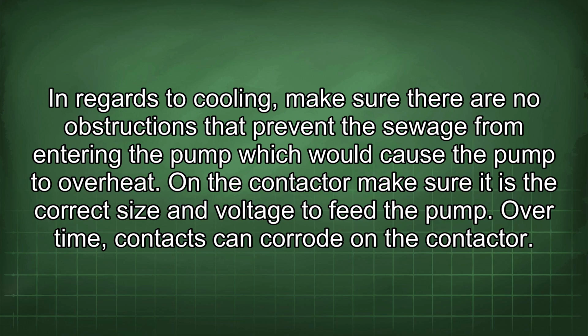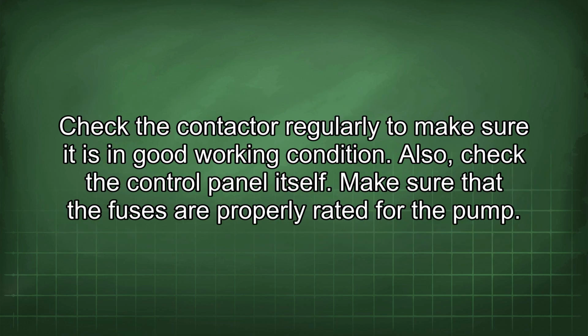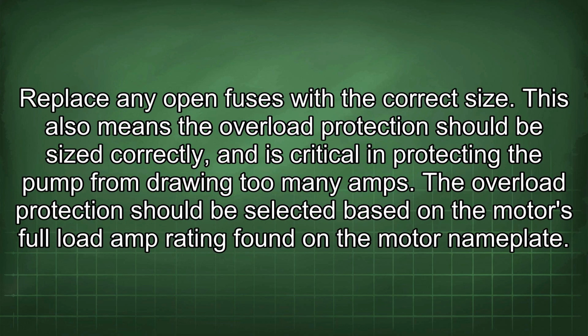On the contactor, make sure it is the correct size and voltage to feed the pump. Over time, contacts can corrode on the contactor. Check the contactor regularly to make sure it is in good working condition. Also check the control panel itself. Make sure that the fuses are properly rated for the pump. Replace any open fuses with the correct size.